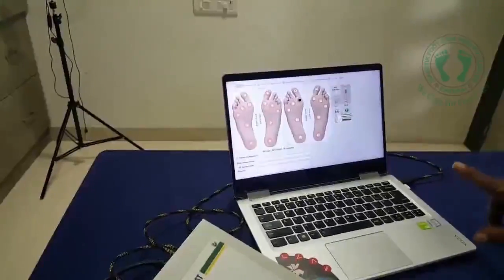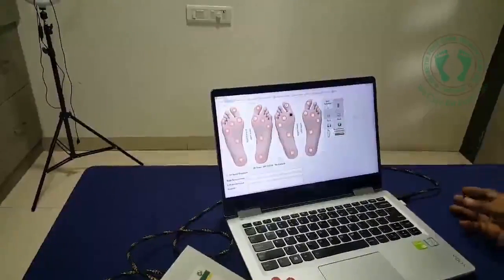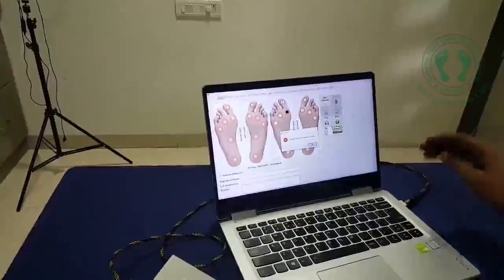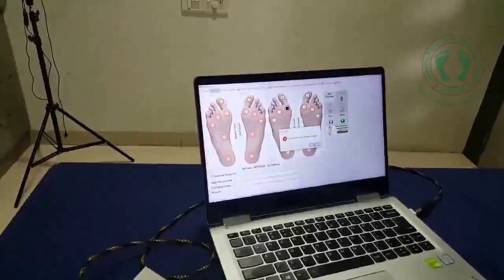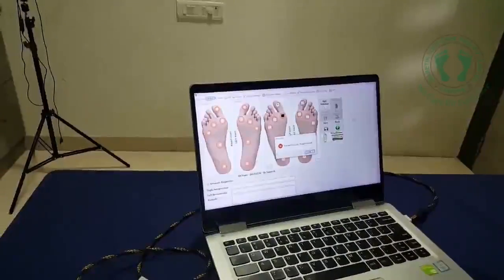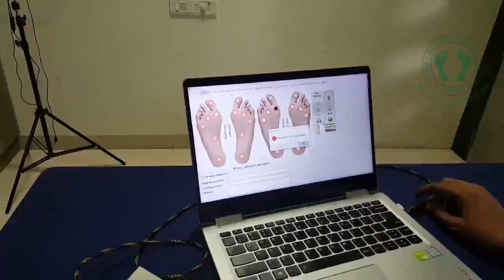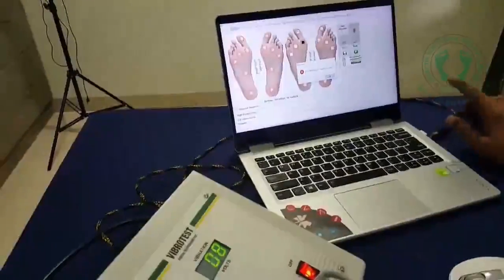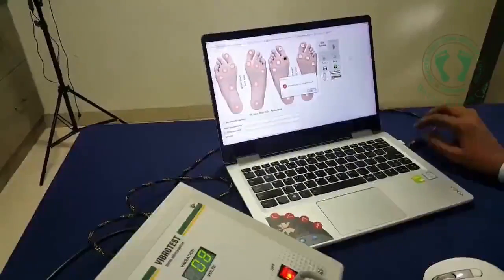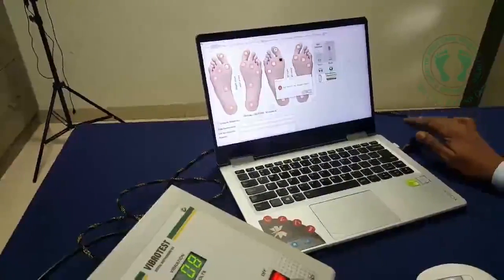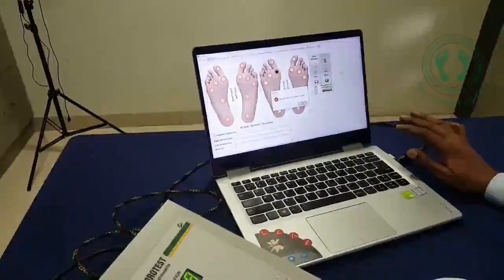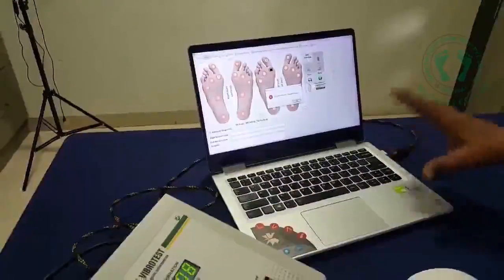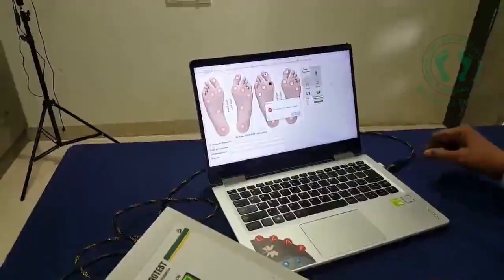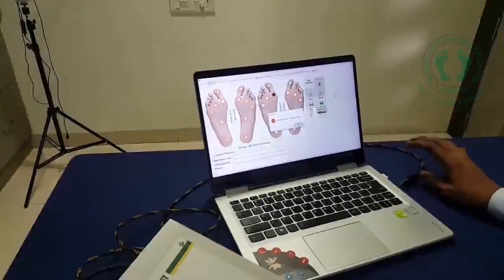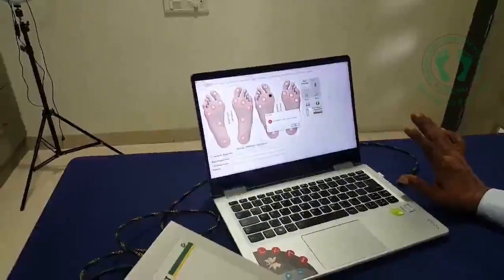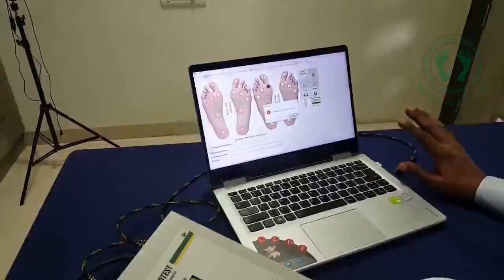Otherwise what will happen, even during the test, accidentally if the power goes or the connection is bad, or I am removing the cable, then it says the port is closed. So you have to be a little careful while doing the test. Before you do the test, see whether the cable is connected and the machine is switched on. Otherwise you will get a communication error. So that's a problem. But once you are keeping it stationary, and machines are not moved, you can just switch it off, switch it on and use it. Nothing will happen. Only when you are using a laptop for some other application, removing it and then bringing it back again and testing, if you forget to connect the cable, then you will have a problem. So this is the only step you have to take care of while connecting the system. Otherwise there are no other issues.